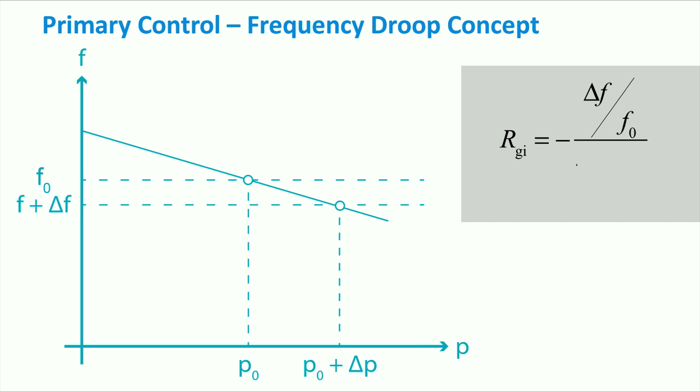The droop of a generator i is defined as the ratio of the frequency change to the corresponding change in active power output provided by the same generator. Note that the power change is given as the percentage of the initial power production, while the frequency change is given as the percentage of the nominal rated frequency. The rated frequency corresponds to the grid frequency, 50 Hz or 60 Hz, depending on the country. Here in the Netherlands, the grid frequency is 50 Hz, for example.